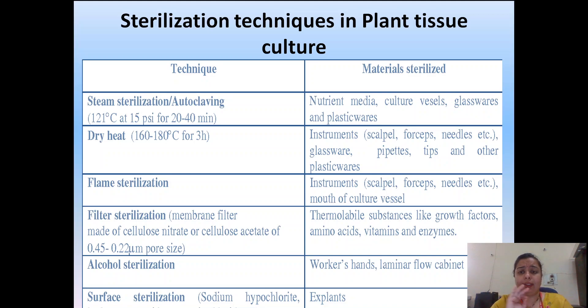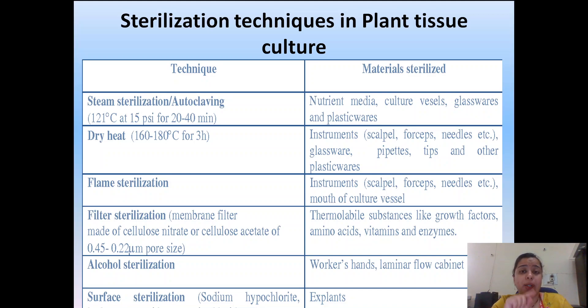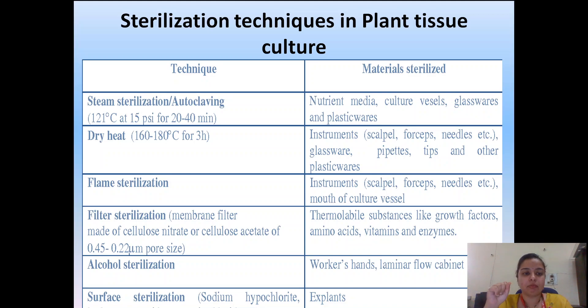For autoclaving, the standard temperature is 121°C, pressure is maintained at 15 psi, and it is done for 30 to 40 minutes. For glassware and plasticware, autoclaving is also applied. Dry heat sterilization is applied to instruments like scalpels, forceps, needles, pipettes, and plasticwares.